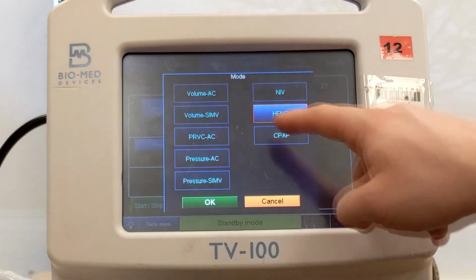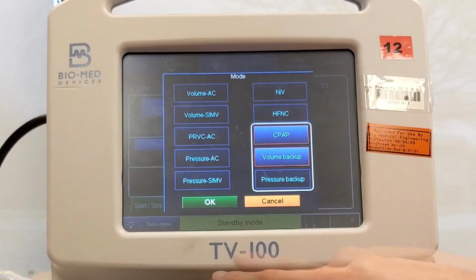Lastly, the CPAP mode is for intubated patients only. While selecting the CPAP mode, you will be given 2 options: volume or pressure backup. These controls are used if the apnea delay time has elapsed and manual breaths are required. Depending on which backup was selected will determine whether pressure or volume will be given as a manual breath.